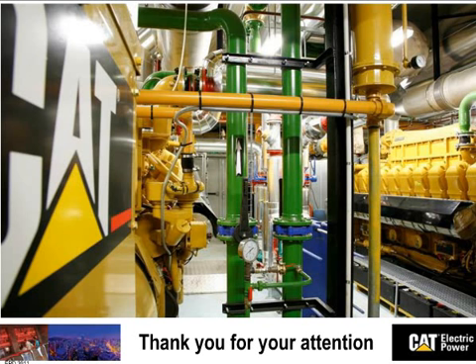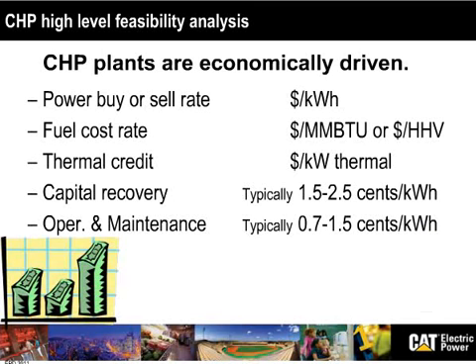And another question, I see a couple people asking questions about the operation and maintenance cost. So if the installed cost is around that $800 per kilowatt, what can one expect for the operating and maintenance costs of a CHP system like the ones we're discussing today? Well, I'll give you a high number, but I know they're always below this. I brought that on one of the first slides. So typically the operation and maintenance cost are between 0.7 to 1.5 cent. This is the last line on the slide here. 0.7 to 1.5 cents of US dollar per kilowatt hour. That's typically what you should calculate, and depending on what you want in your service, depending what insurance you want on your power, on availability, the price may differ. The quality of gas also makes a difference.